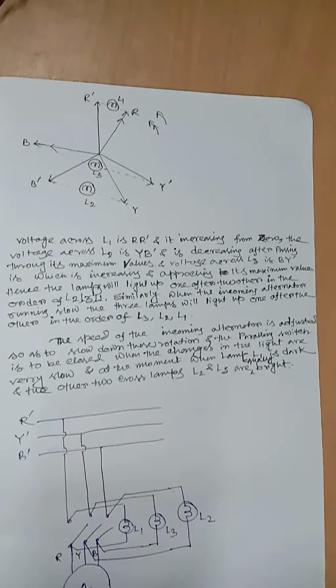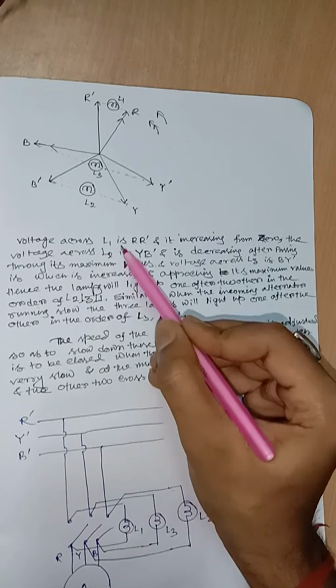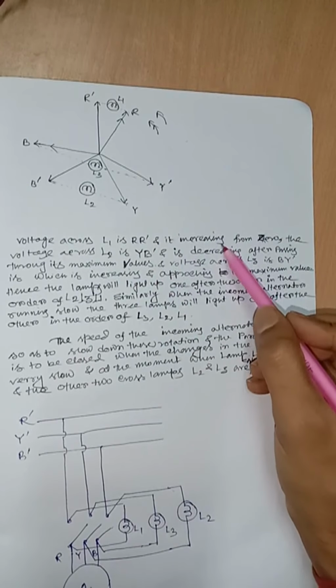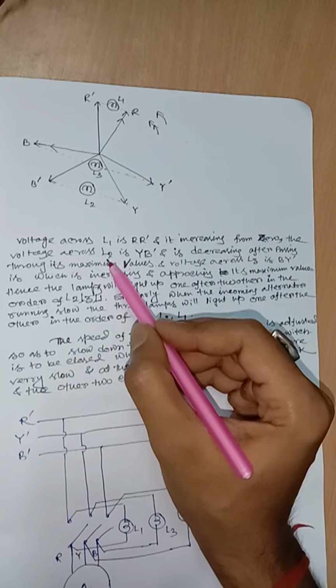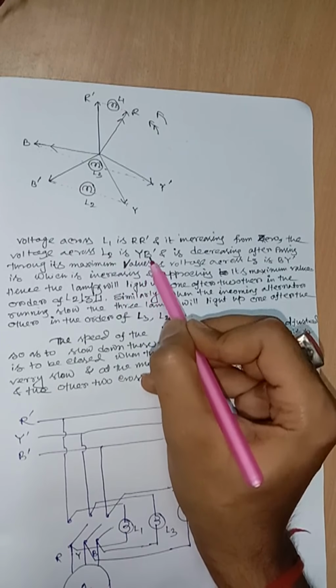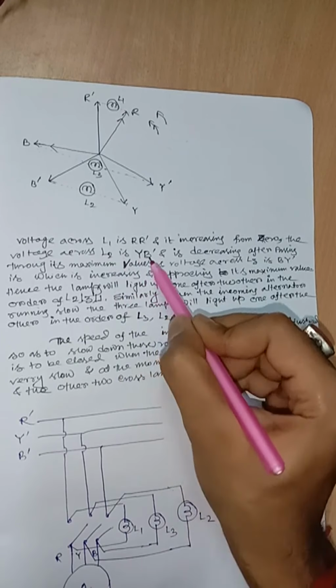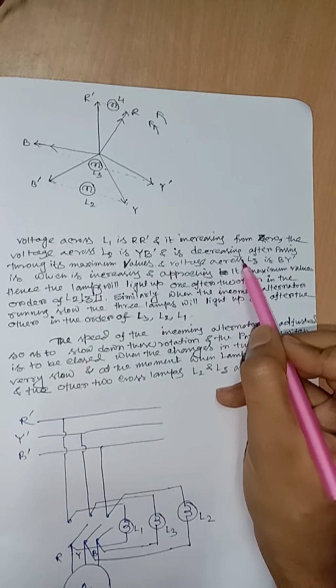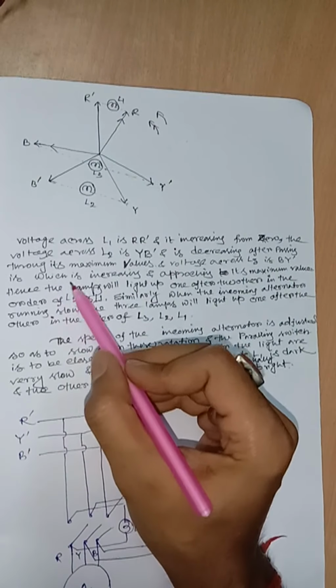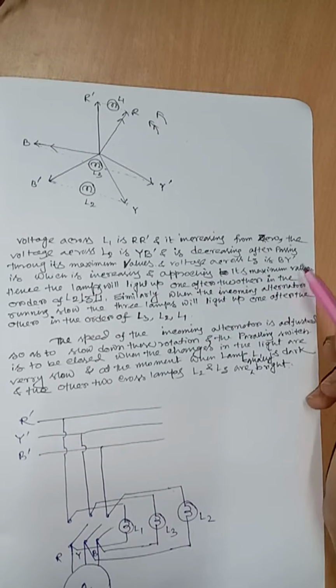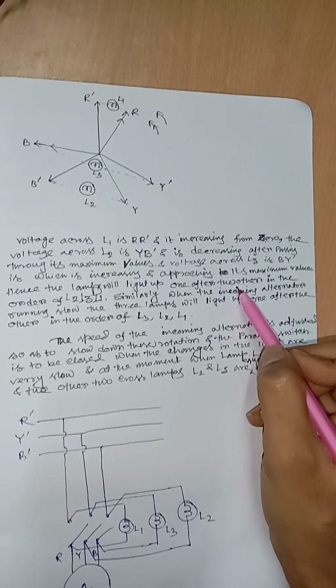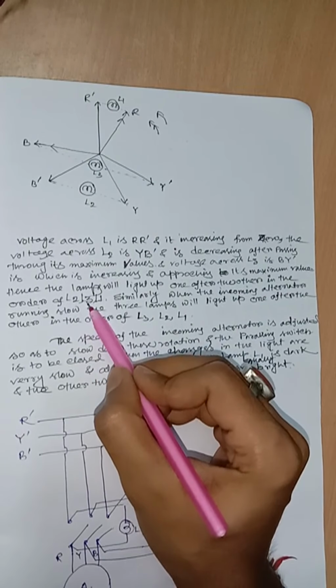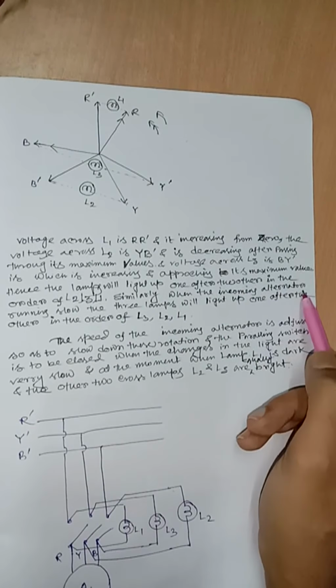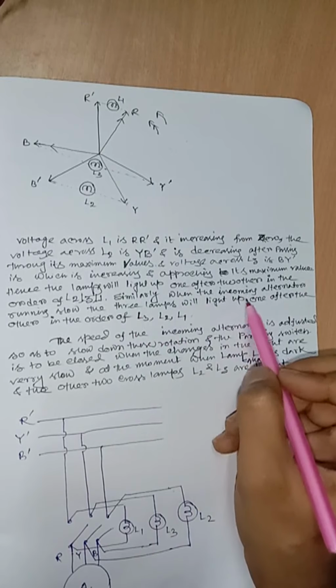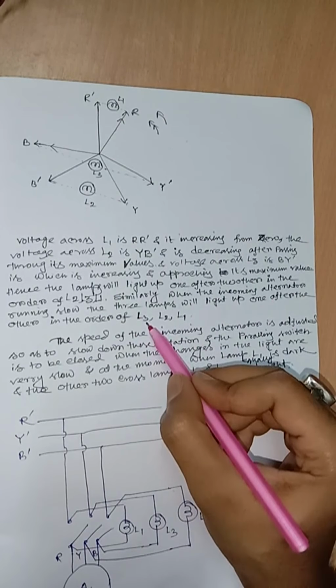The reason behind that: the voltage across lamp 1, that is R R dash, is increasing from 0. The voltage across lamp 2 is Y B dash, and is decreasing after passing through its maximum value, and the voltage across lamp 3 is B Y dash, which is increasing and approaching its maximum value. Hence the lamps will light up one after another in the order L2, L3, L1. Similarly, when the incoming alternator is running slow, the three lamps will light up one after another in the order L3, L2, L1.